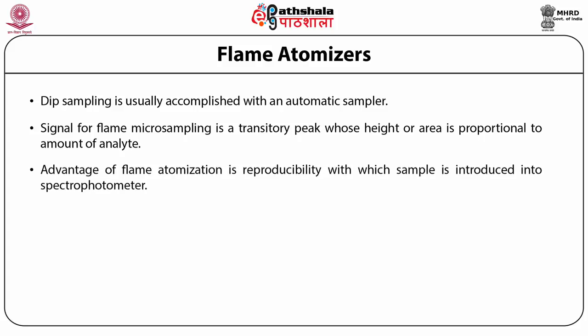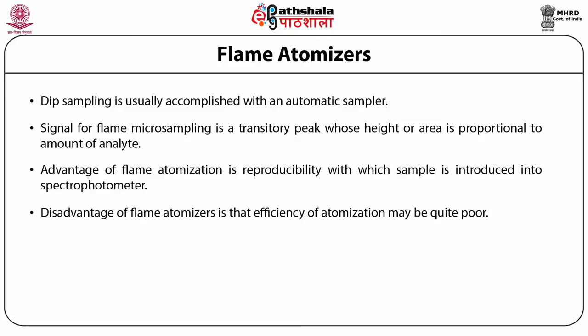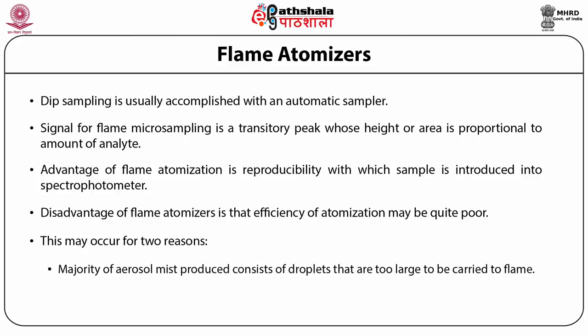The principal advantage of flame atomization is the reproducibility with which the sample is introduced into the spectrophotometer. A significant disadvantage is that the efficiency of atomization may be quite poor. This may occur for two reasons. First, the majority of the aerosol mist produced during nebulization consists of droplets that are too large to be carried to the flame by the combustion gases. Consequently, as much as 95% of the sample never reaches the flame.